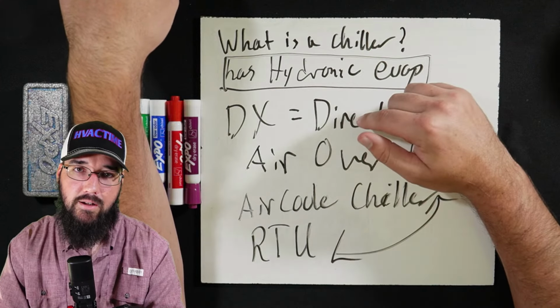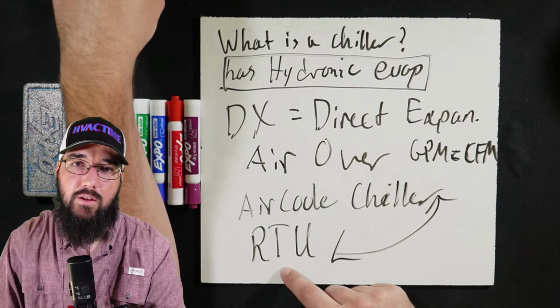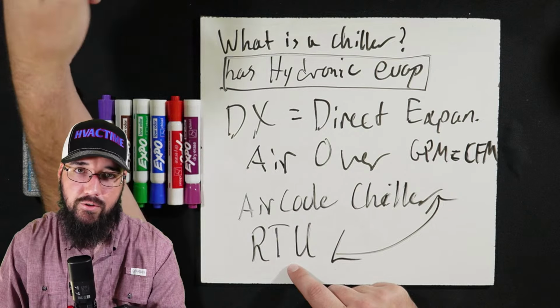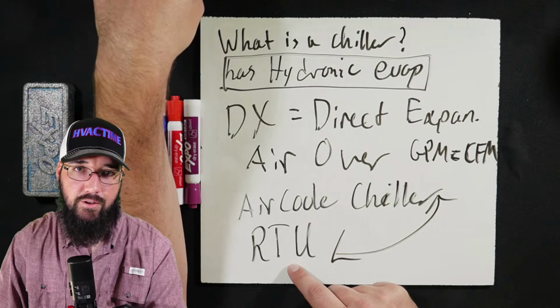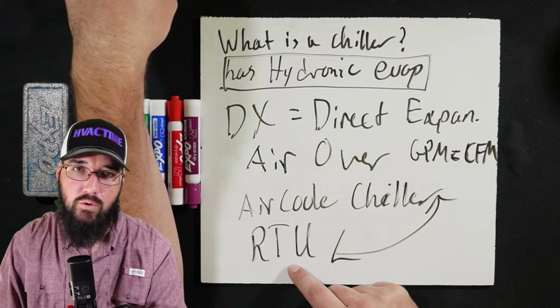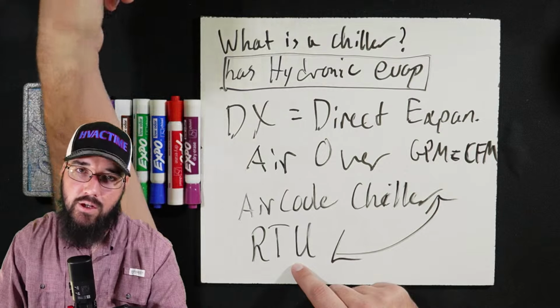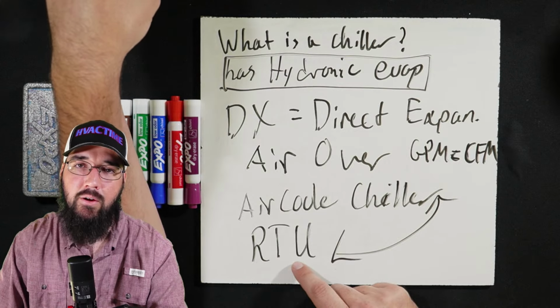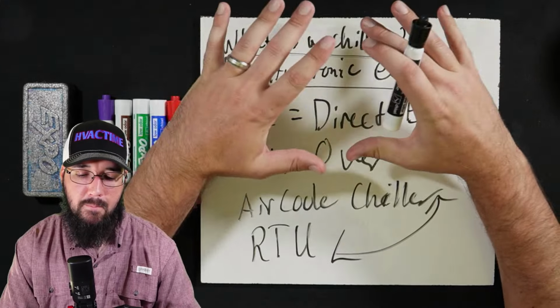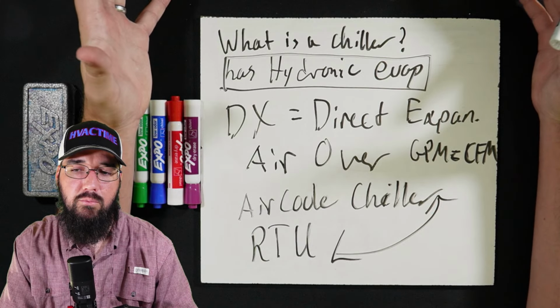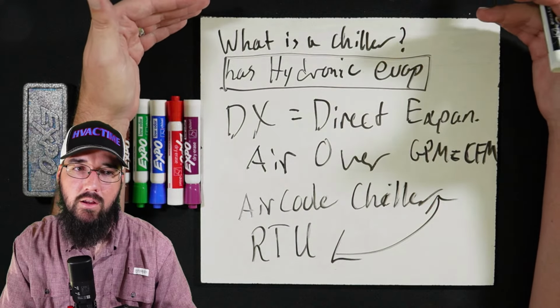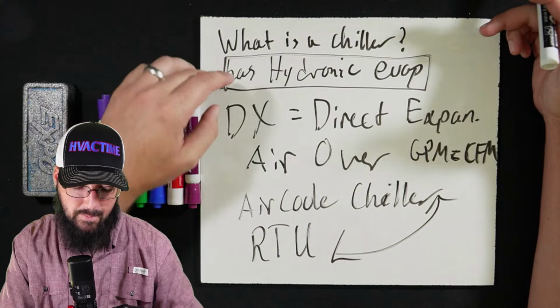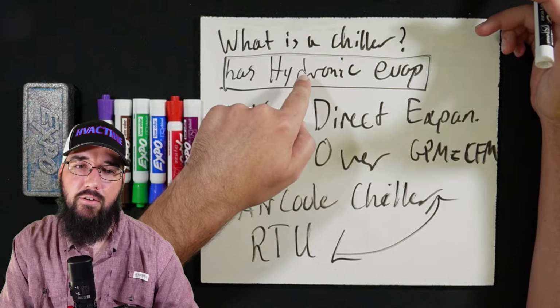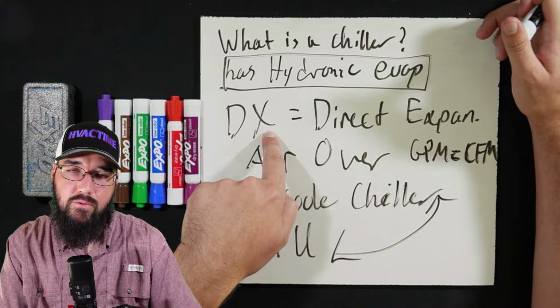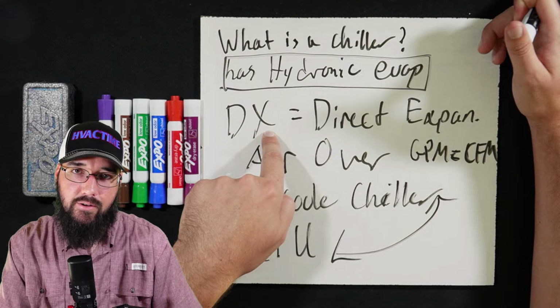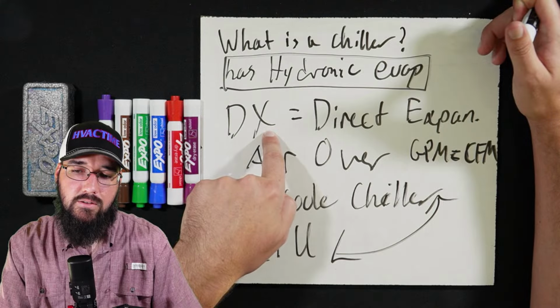The point is, though, it gets more complicated, right? We wouldn't expect to see screws in a RTU system, like a package unit on the roof. We wouldn't expect that, even at 300 and 400 ton RTUs with 25 ton scroll compressors in them. Again, they're scroll, so that changes how that machine's going to function, how it's going to control capacity, things of that nature. But everything else ends up staying cross-compatible in terms of how we would troubleshoot the process. But that's all this comes down to. A chiller is going to have water going through the evaporator. A DX RTU is going to have air going across the evaporator. That's it.